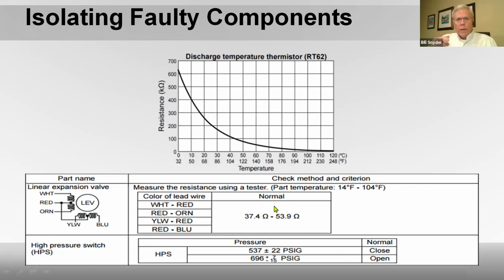It's like a motor winding. It spins the linear expansion valve up, and spins the pin down to like 2,000 steps in some positions. And that's the way they do it. So you can actually check the resistance and see if it's open or closed.